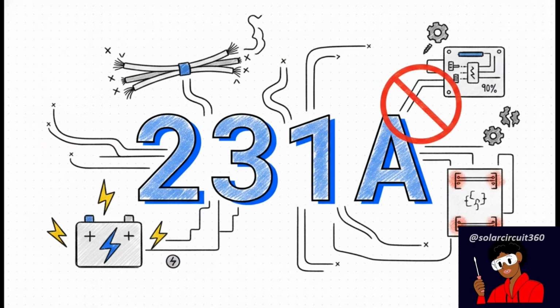But wait, because no inverter is 100% efficient, right? When you factor in a standard 90% efficiency rate, that number jumps up to an astonishing 231 amps of continuous DC current. That is an enormous amount of electricity to be pushing through wires, terminals, and internal computer boards. This right here is exactly why large systems create extremely high DC currents, and honestly, it's exactly why they fail if they aren't engineered perfectly.